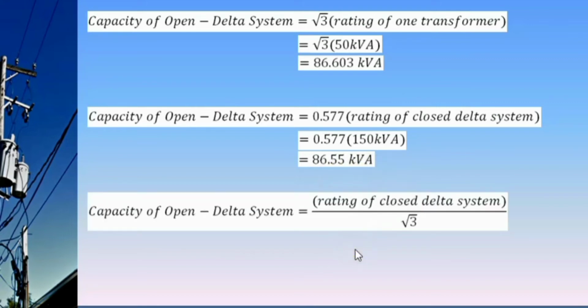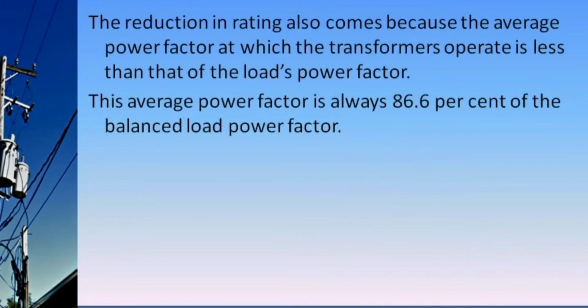If we divide the equivalent closed delta system by square root of 3, 150 kVA divided by square root of 3, this will give us 86.603 kVA. Whatever solution we use, we should arrive at exactly or nearly equal values. Another reason for this reduction in the ratings of the system comes because the average power factor at which the two transformers will operate is less than the load's power factor.